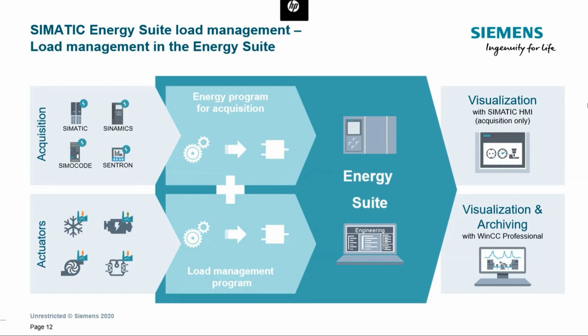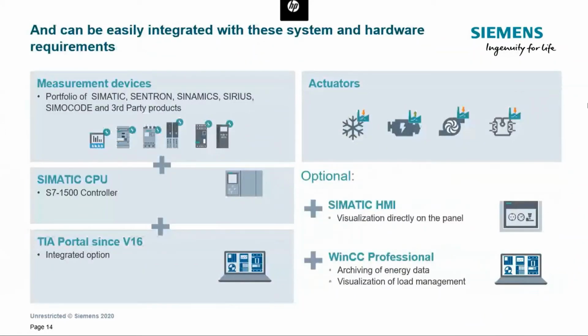The blocks required for the data processing are generated automatically, and not only that, even the visualization is generated in an automated way. So it means you configure the devices, generate the blocks automatically, and that information becomes available. If you have the system, those blocks are available in your controller, and if your controller is connected to a SCADA system, namely WinCC Professional, you can also automatically configure a data log that will log the energy values.